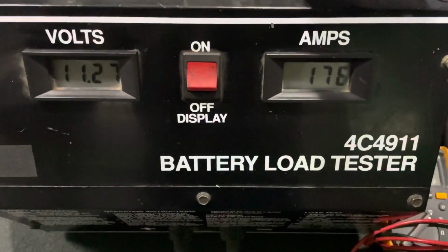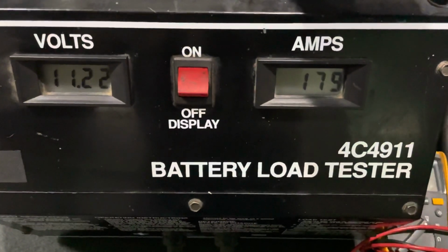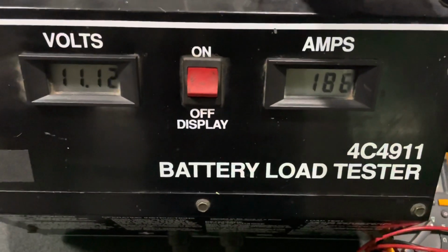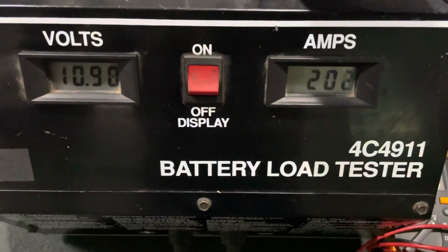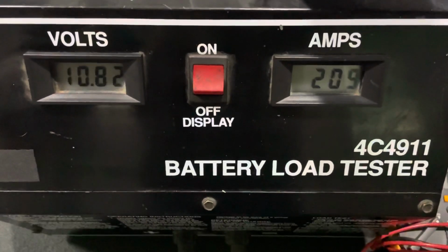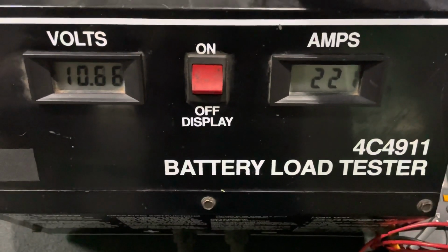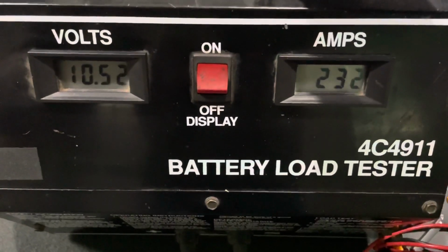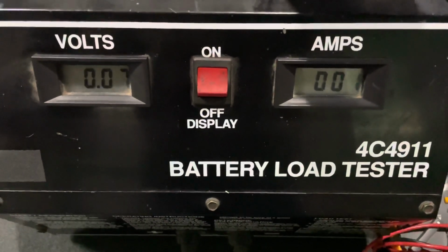There we go, voltage starting to drop. We've got 170, so I've gone past the limit. It's still clamping up, still adding current. 200 amps now, and it's going to cut out on low voltage disconnect.